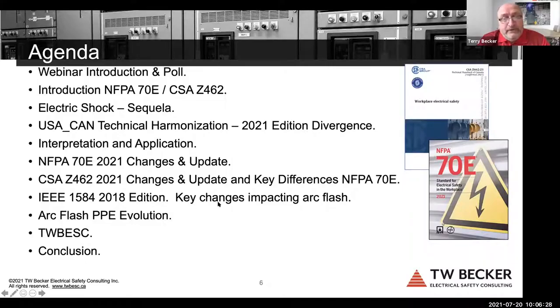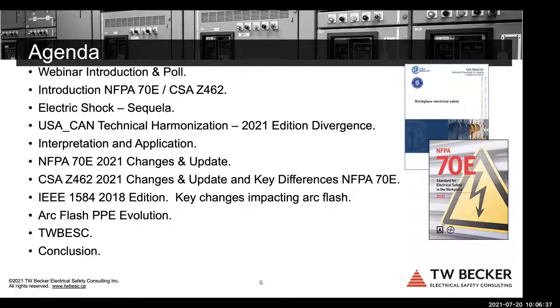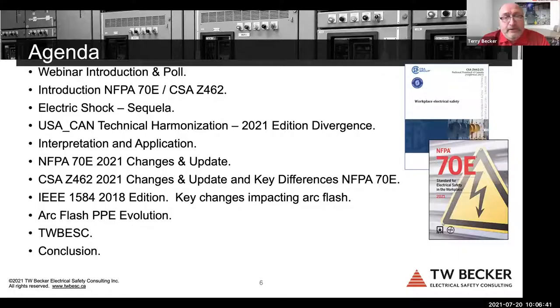And then IEEE 1584, key changes. Well, there are significant changes in the new formulas that were published 2 years ago. And again, I'm concerned that we're maybe getting some conservative interpretation of 1584. And the parameter selection that's now new may not be selected appropriately or conservatively, and we'll highlight that. Arc flash PPE evolution.